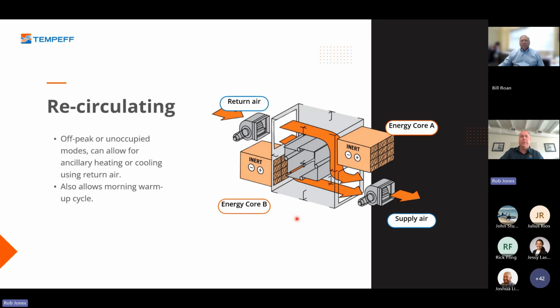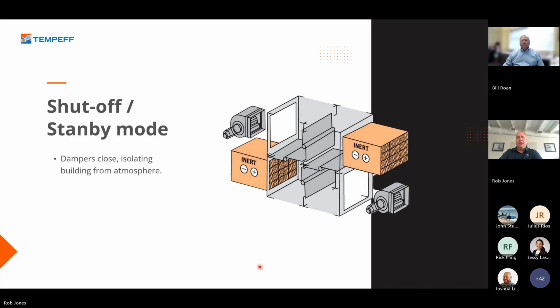This gives us the ability to do a morning warm-up cycle if the unit is shut down to prevent a cold blast of air when the unit first fires up. You would do this 15 minutes prior to the building being occupied. The cores are charged and ready to go. We also have a shutoff mode, so if the unit is completely off, we'll configure our dampers to isolate the building from the outside atmosphere. These are all standard features.